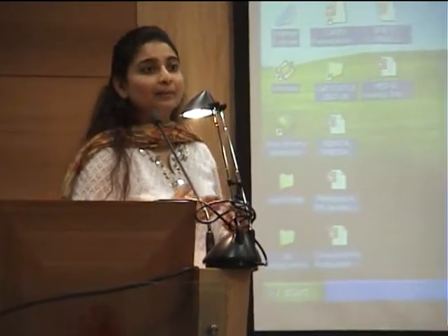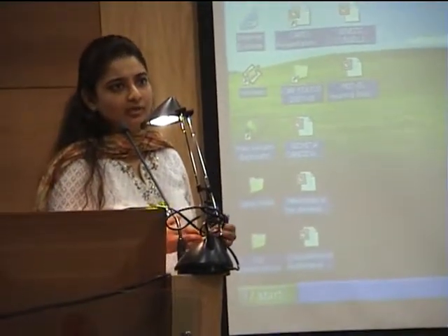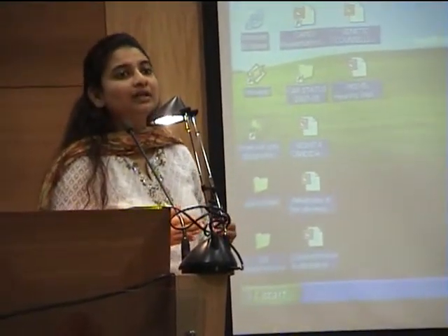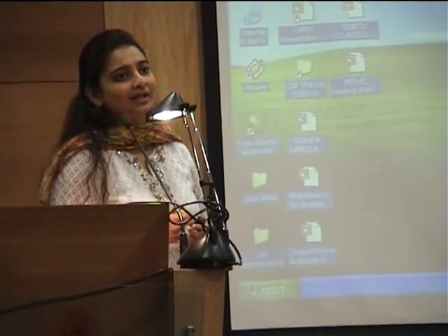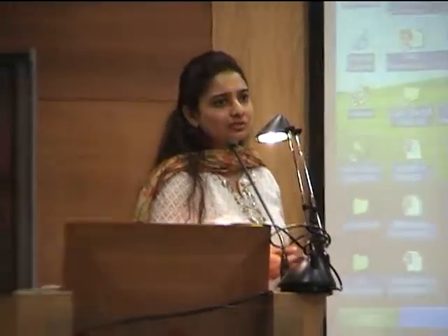But mapping at least once a year, after say 2 years of implant use, has to be done, because as I told, it's not only setting the parameters but it's also a diagnostic tool.